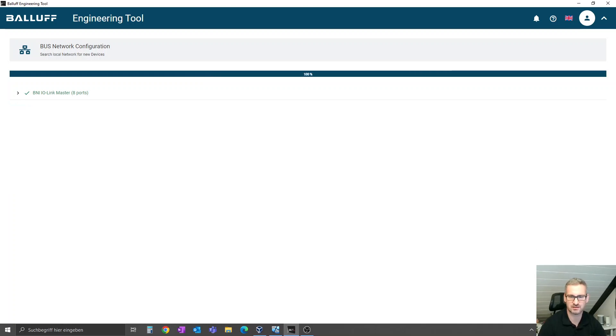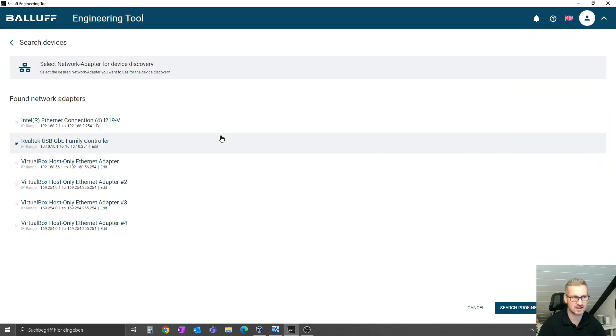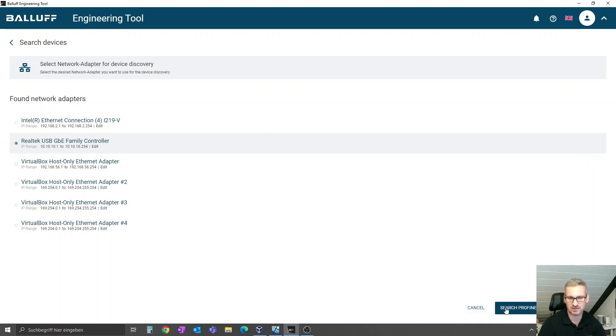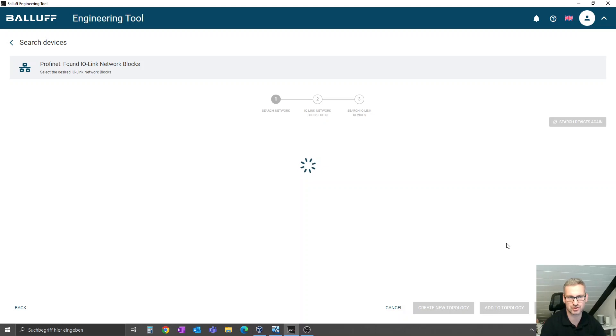Next step is to scan the network. You have to discover your controller on the left side. On the right side you will find two possibilities: the Profinet scan or the Ethernet IP scan. In our case, the BNI 00HL is a Profinet device, so we click on the button search for Profinet. This will proceed as before and discover the Profinet connected devices.